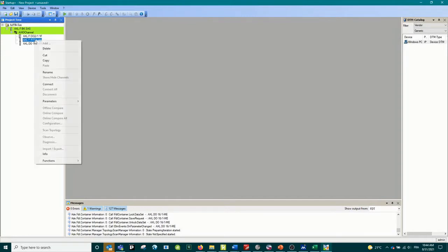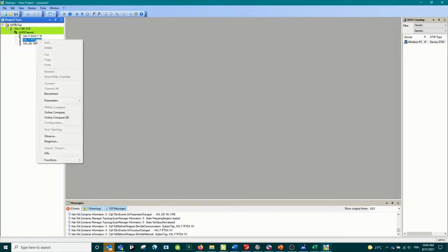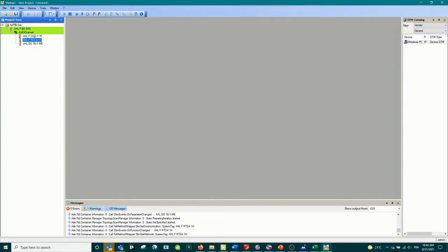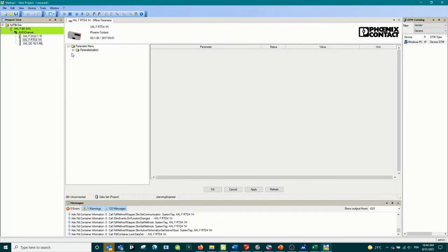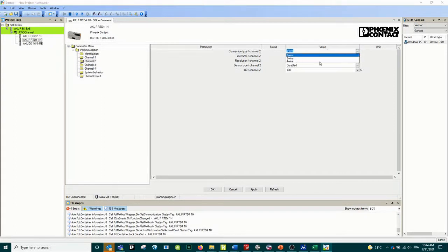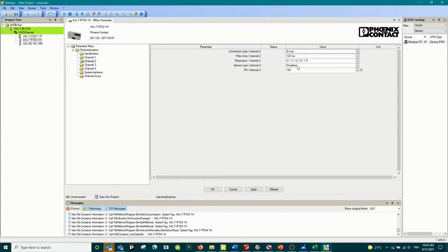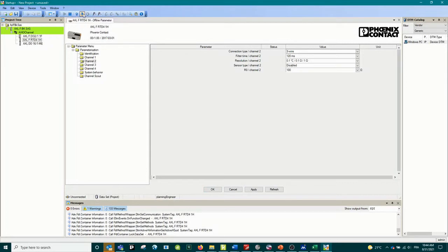First we're going to go online with this. I double click on it and it's going to open all parameters and I got all channels over here. Let's say in my channel 2 I would like to change the settings, so I just pick whatever I want and press apply. When I press OK I will download that new configuration into the bus coupler. If you don't remember the configuration it's possible to upload the configuration and you can also use that arrow to download that configuration.